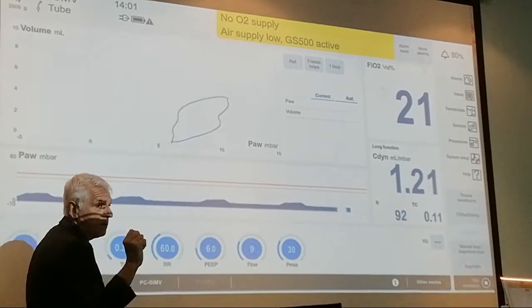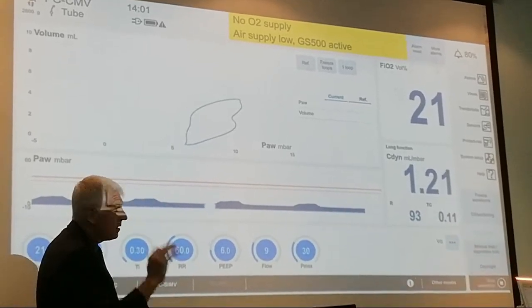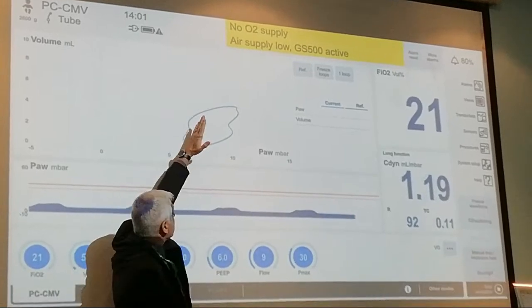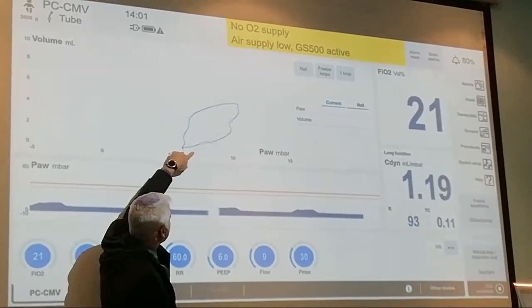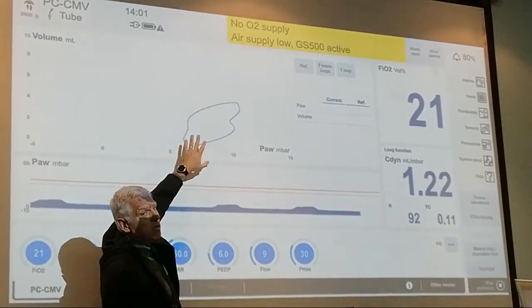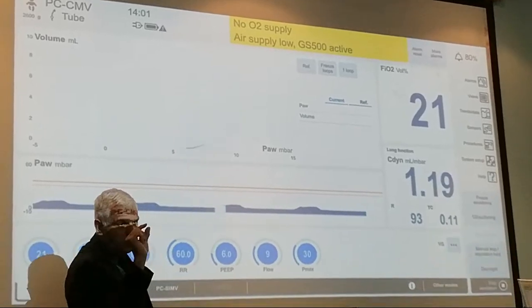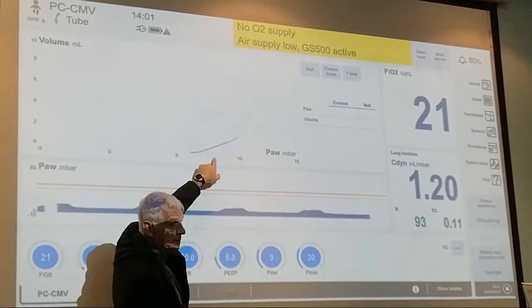Ideally, you want to have the opening pressure right at your peak. So the curve should start right away. Don't have any flat portion. This is not too bad. Sometimes you get a small portion, but it shouldn't be very flat.